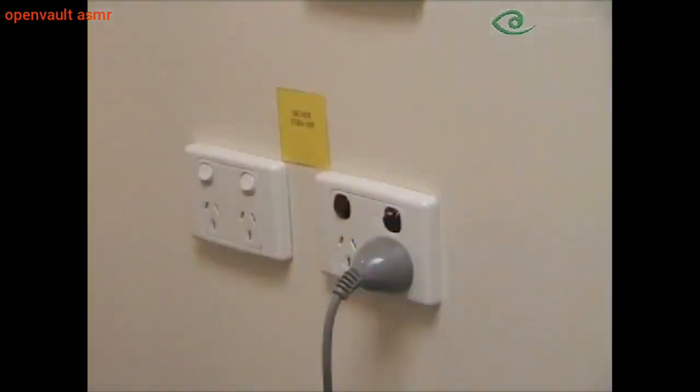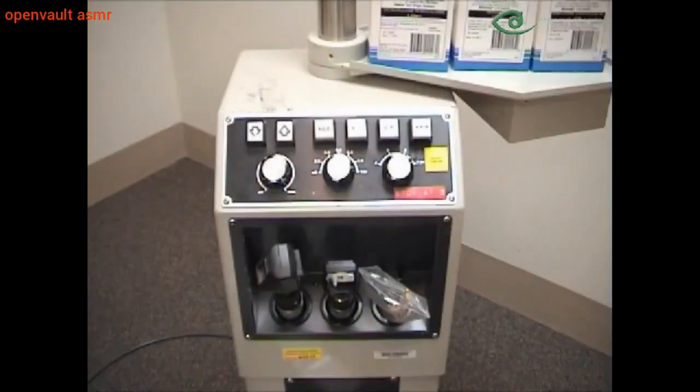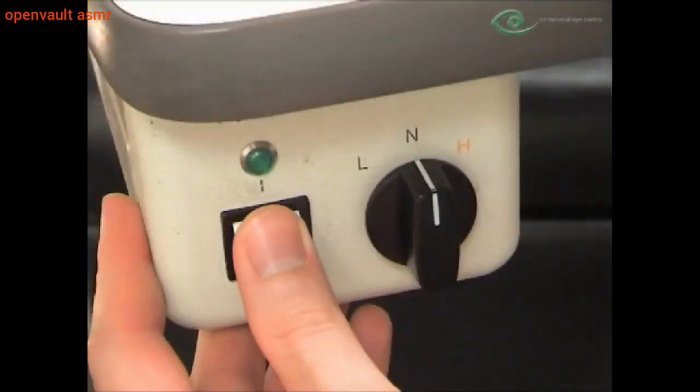Sometimes you sit down at the slit lamp and you can't get it to turn on. If that happens, run through these steps. Make sure that the slit lamp is plugged into the wall and that the wall outlet is turned on. Some slit lamps also have a main switch located on the centre column. Turn that on.